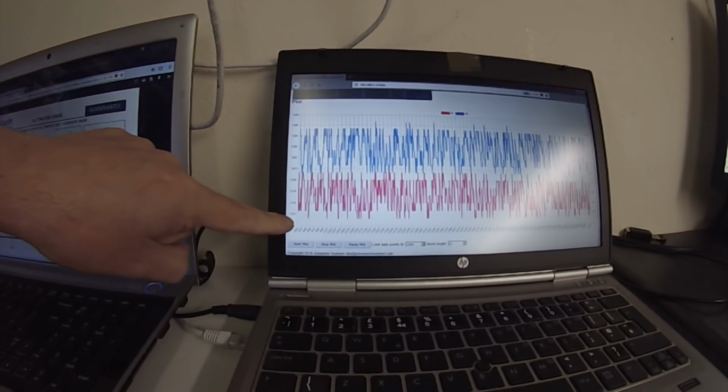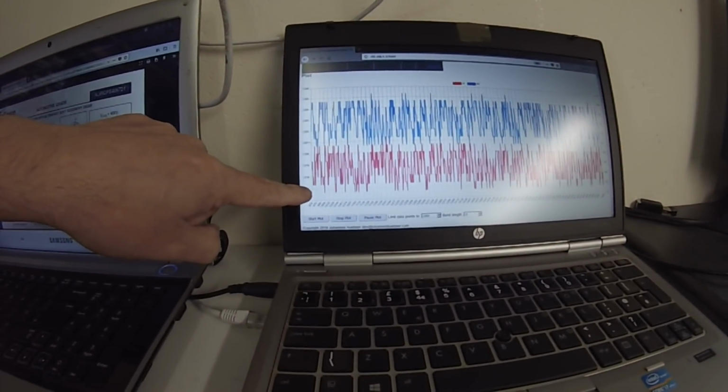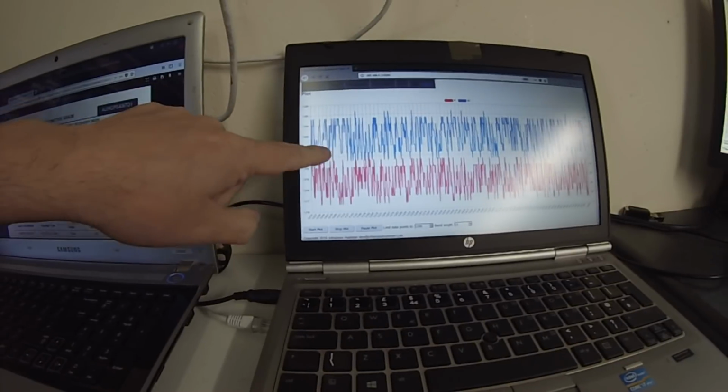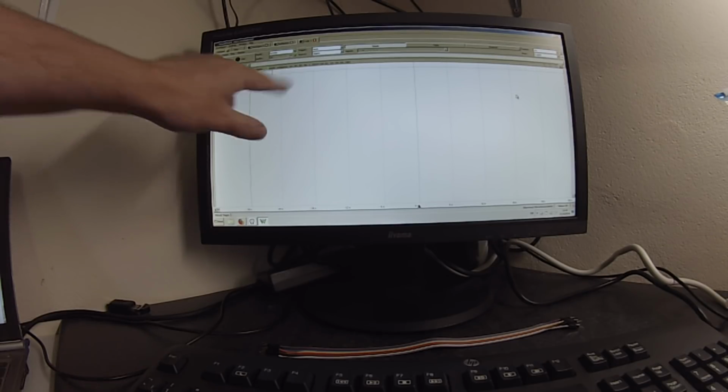As we can see here, we've got a jitter now between about 1217 and about 1224 amps, which is perfectly fine, because having dead accurate current readings is not required for the Hubner control system. And if we look at our logic, we'll see that we're at logic 1. I'm just going to slow down the pace of this logic analyzer here. I'm going to put it on 6 seconds per division. So you'll see it's just plotting across slowly now.